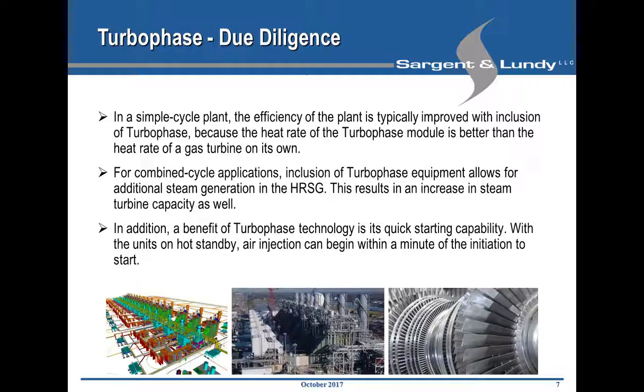The reason is the gas turbine typically requires two thirds of the heat input to be used to drive the compressor, and one third of the thermal power is actually only available as electrical power at the generator. Since this air is compressed externally in an external compressor, you have a significant efficiency advantage for those additional megawatts generated in the turbine. And in combined cycle, you again have the advantage of the increased mass flow in the turbine going into the heat recovery steam generator, which will increase the steam flow and thus also the steam turbine capacity. So you have a double impact, increasing the gas turbine power output as well as the steam turbine power output.